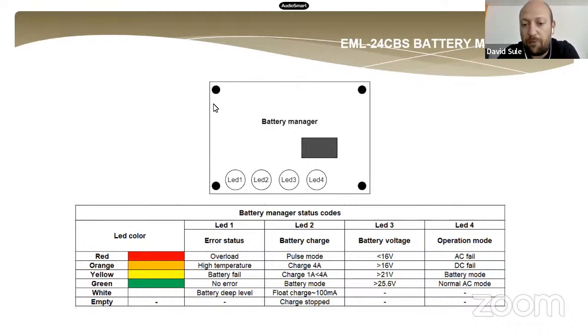For example, if the battery is fully charged, the LED 3 will show the battery voltage information. If this LED is green, that means the battery voltage of the two batteries connected to each other is more than 25.6 volt. If the LED 4 shows green, the panel is in normal AC 230 mode. We can read all of this information from the programming software. We can read it directly from the LCD screen, and we can read if anything happened with the LCD directly from the battery manager, which is installed under the LCD.